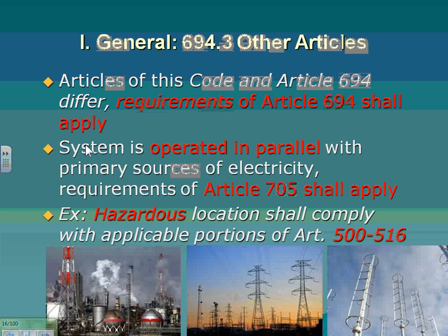And if you have a hazardous location, I sliced it a lot because it's a new article, and I will be teaching it to our students. So I thought I'd just go through the details. I want to spare you: if you're installing this in a hazardous location, what do you need to do? Well, you have to adhere to the hazardous location rules, right? And if you run them in parallel, you also have to adhere to the rules of 705. Article 705 is the parallel, meaning you have to sync them before we drop them to the grid. You have to identify all sources of power. You have to have a disconnect from every source of power, and so forth.